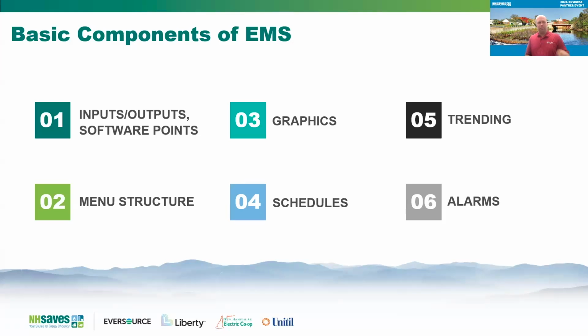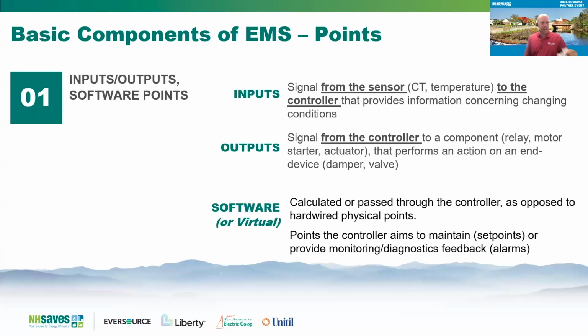So I'm going to focus on a couple of these, one being the inputs and outputs. This is a really important aspect of controls because when you're looking at a point, you've got to know whether this is an input to the controller or an output from the controller. So, for example, a fan status point is an input into the controller.